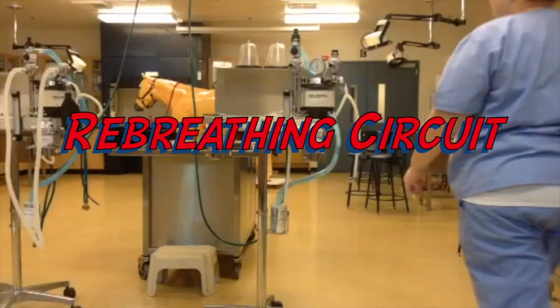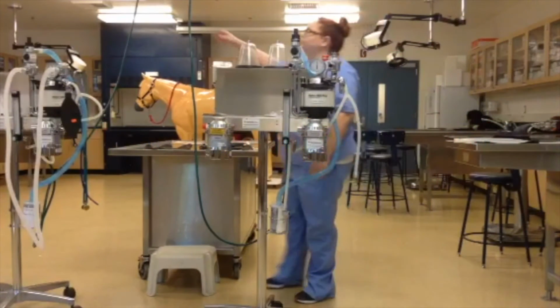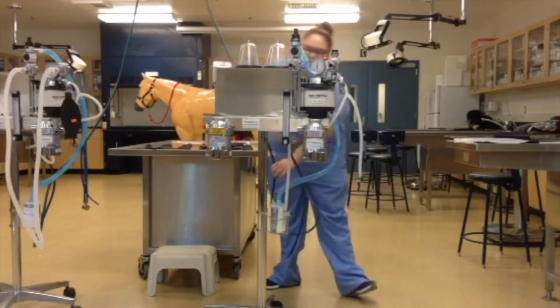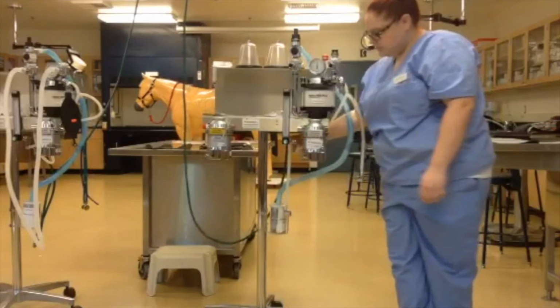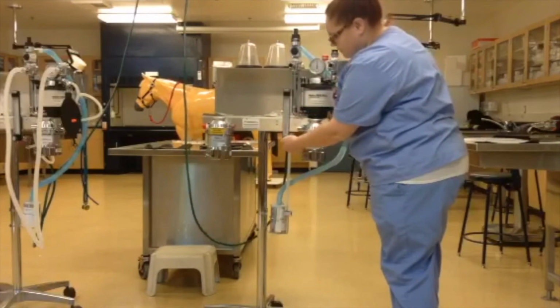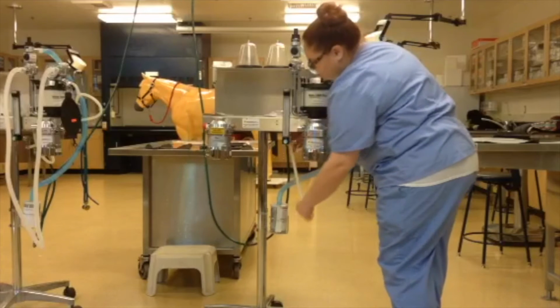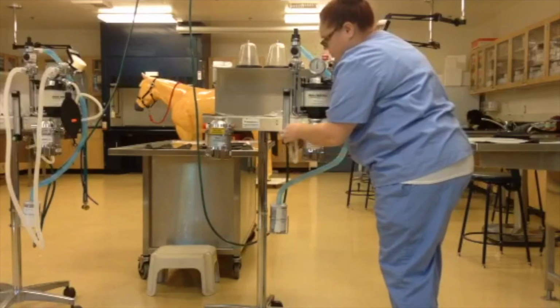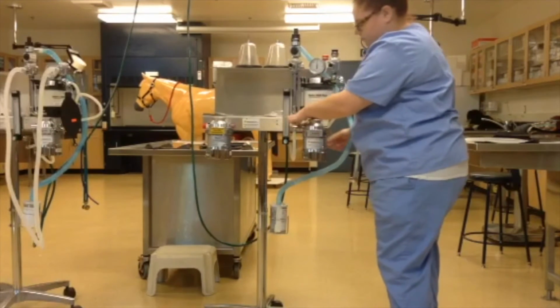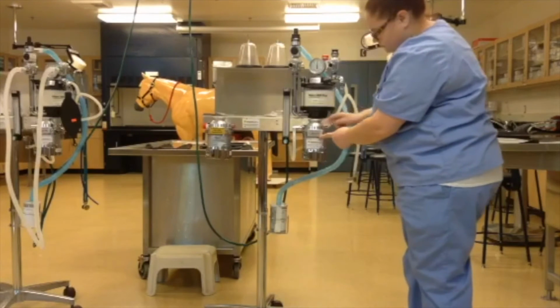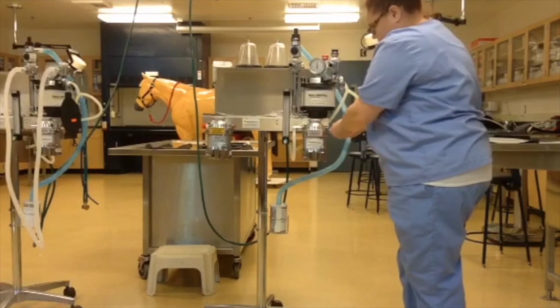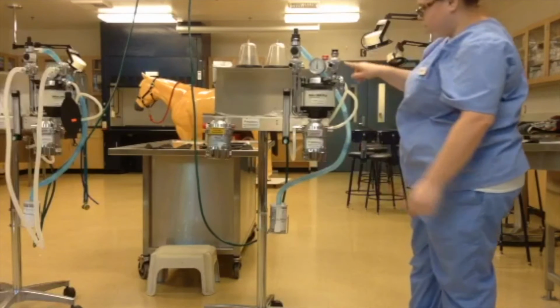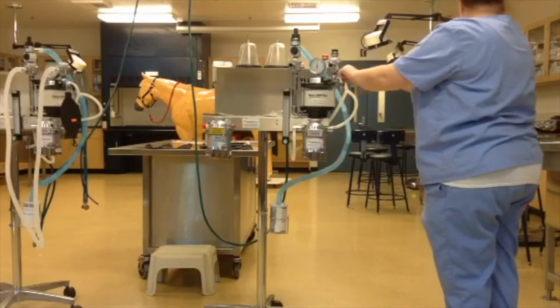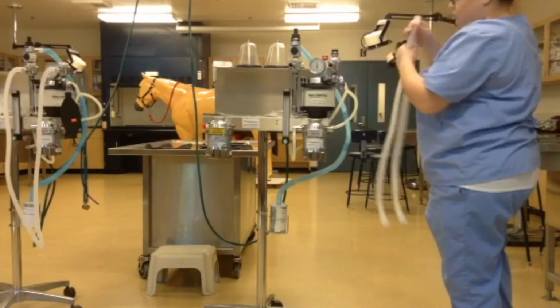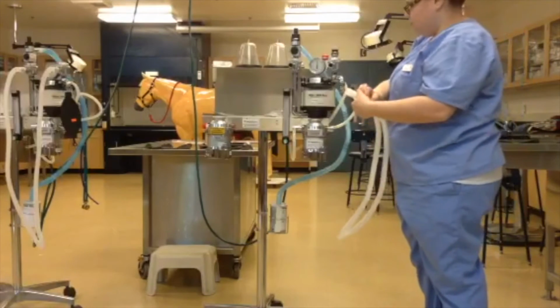Now we're going to set up for the rebreathing circuit. I'm checking that our oxygen supply is connected to our flow meter, and our flow meter is at 0, which also connects to the oxygen flush valve. Now I'm connecting the inlet port for the oxygen, and now I'm connecting the outlet port, which has oxygen and anesthetic. The tube then connects to the fresh gas inlet, which is then connected to the inspiratory unidirectional valve.